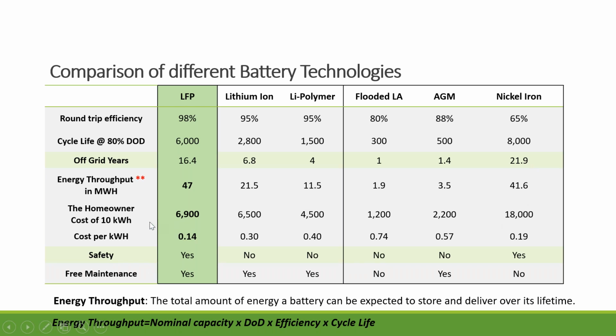So here is just a suggested retail price. If you take that cost and divide it by 47 megawatt hours, that's how you get 14 cents with the LFP chemistry. And looking at flooded AGM, it's much more, you're talking about 3 or 4 or 5 times more. Nickel iron is pretty good, but the challenge is that it's very bulky, you need maintenance, and also the initial investment is very high. So we don't see too much of it in home applications. It's pretty much for large projects or utility scale projects.